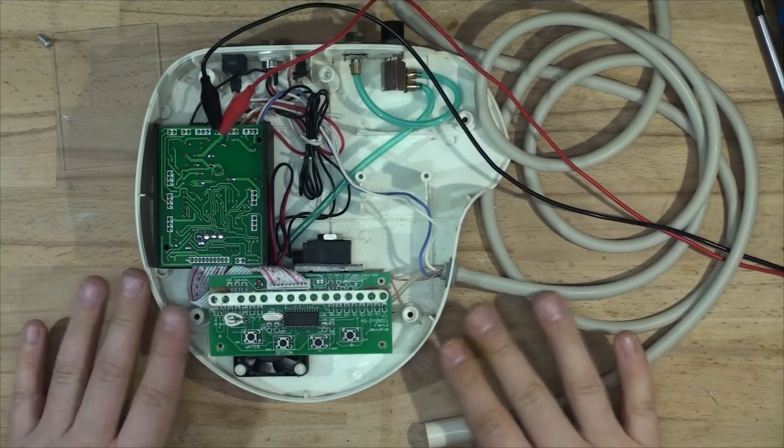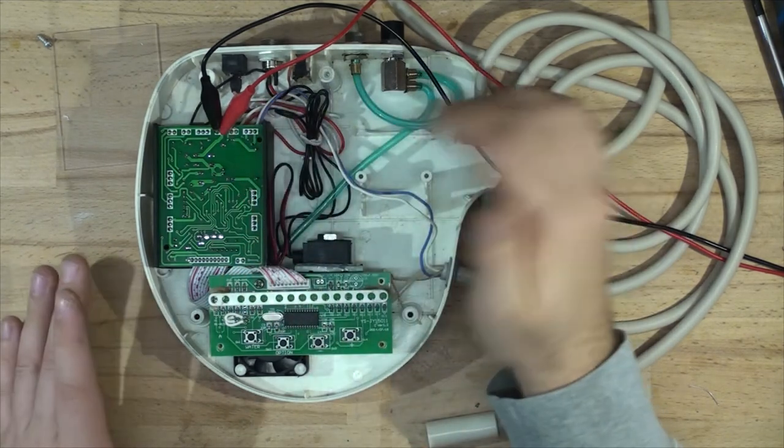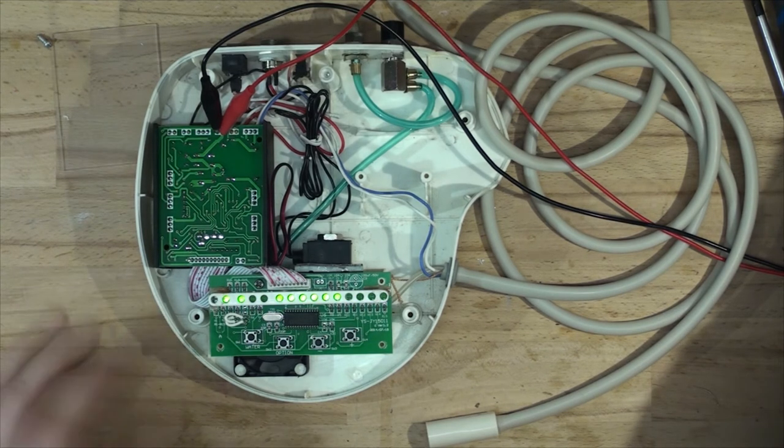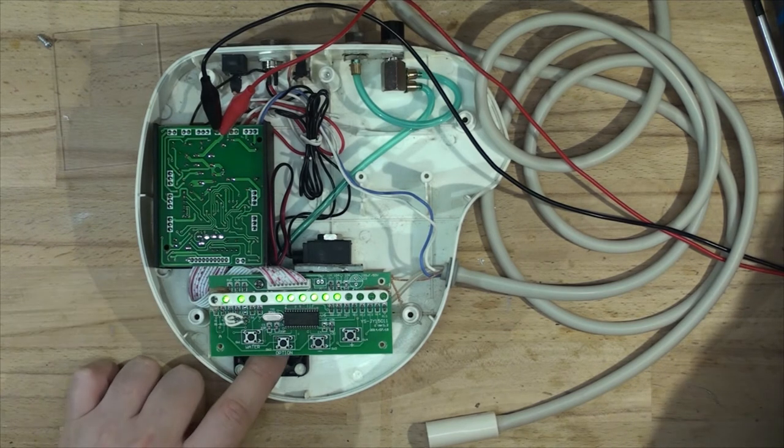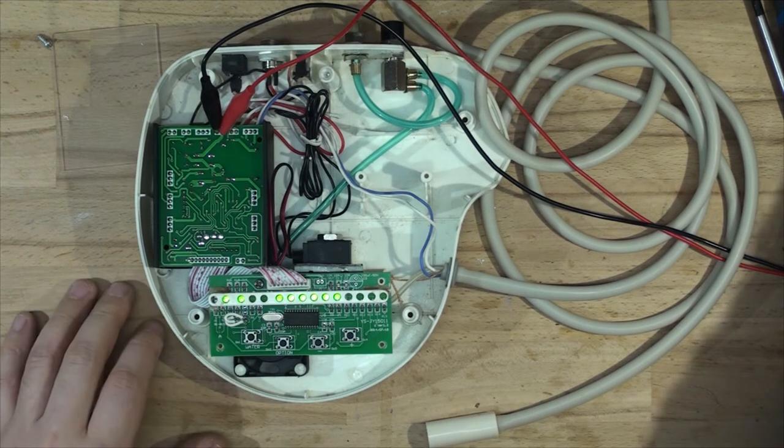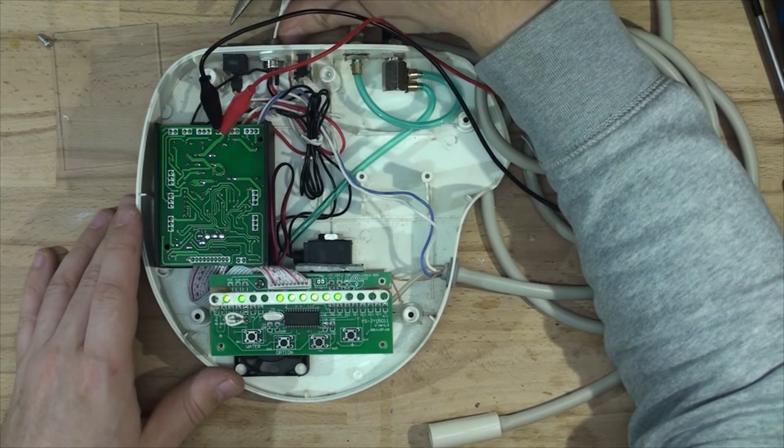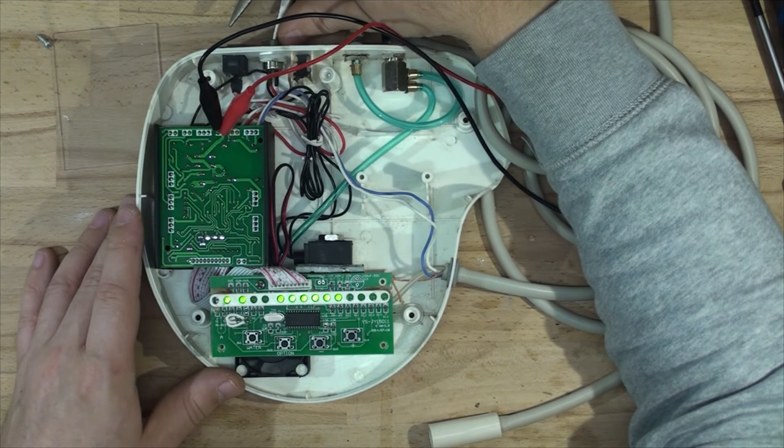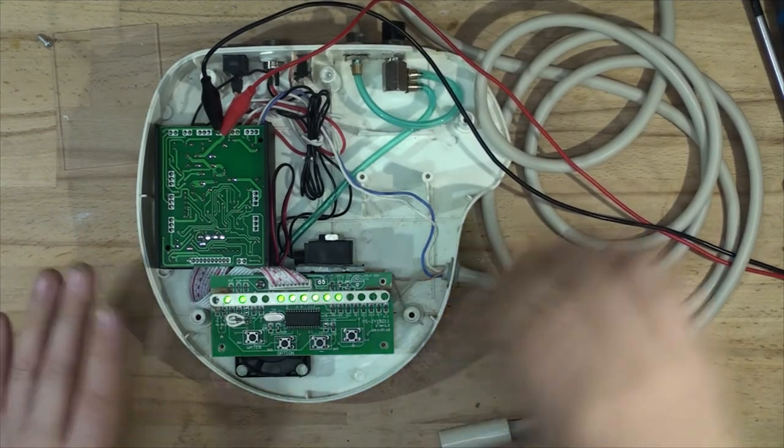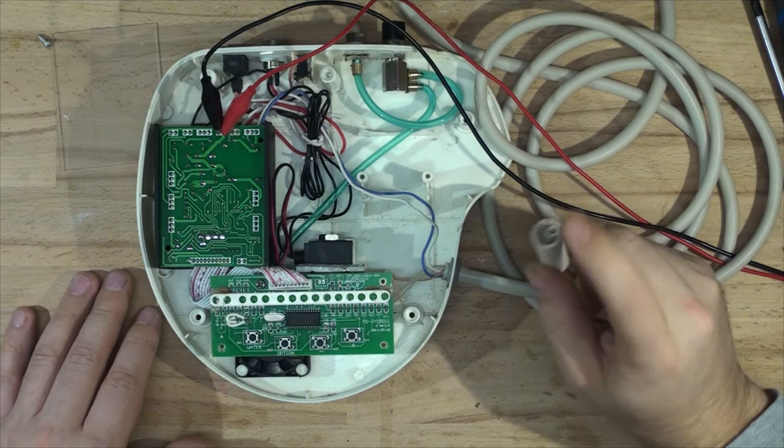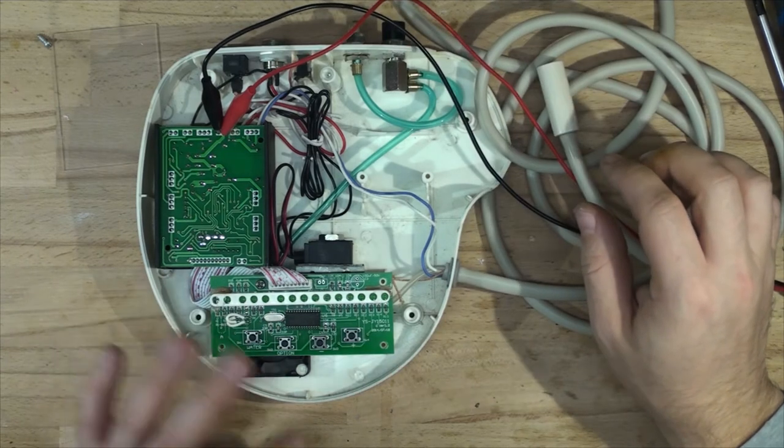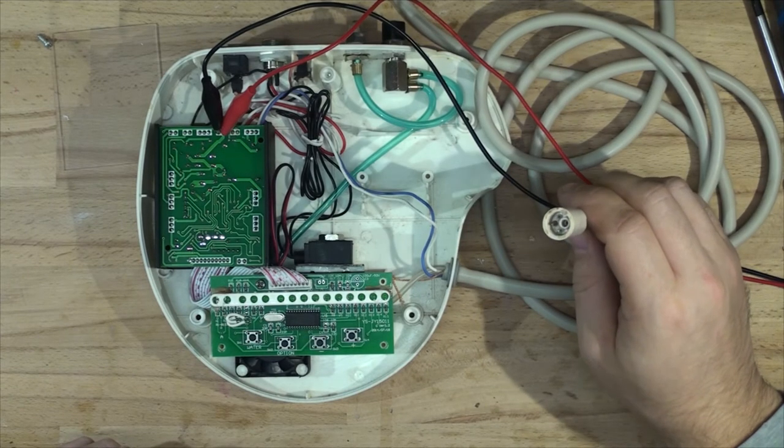The device is now assembled, almost fully ready to plug in. I've got 24 volts DC supplied directly to the power supply of the unit. Let's power up and see what happens. It looks like it's working. It's consuming 163 milliamps at the moment. The fan, however, definitely needs to be replaced. The fan is really noisy. Let's try triggering it to see what happens. The valve is working just fine. It seems to be working fine. I haven't got the tip on, so we'll scope it as well to make sure. Let me just quickly replace that fan so it's not noisy.